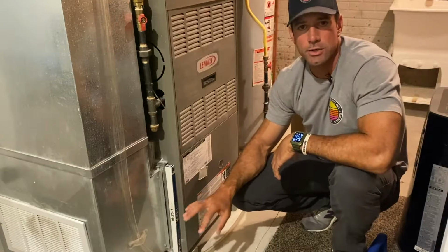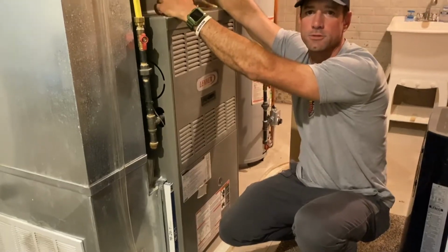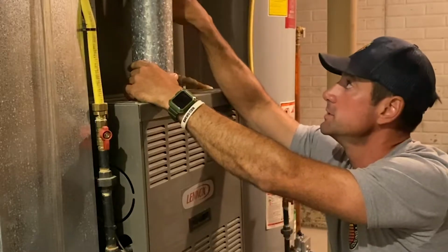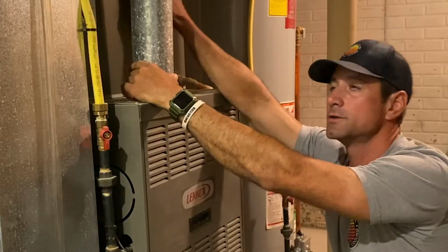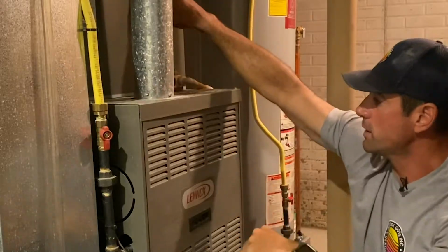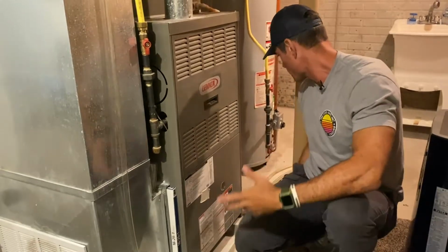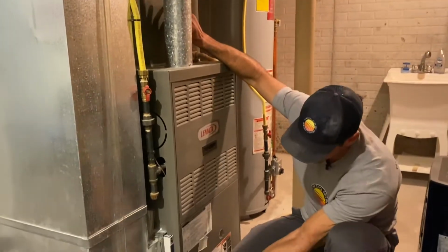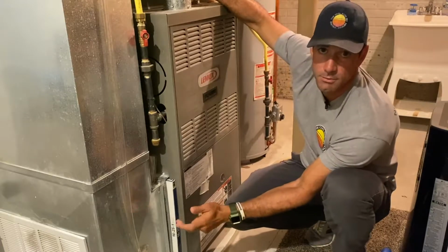If it gets too dirty, then your coil will get too cold. So your coil up here won't have the warm air from the house blowing over it. Basically, it just doesn't have that warm air, so it just gets colder and colder. Once it gets to freezing temperatures, all the condensation from your house freezes onto the coil, turns it into a block of ice. At that point in time, you'll notice water on the floor around your furnace. You'll be like, where's this water coming from? A lot of times it's from a frozen coil, and it's caused a lot of times from a dirty filter. There can be other causes, but those are going to be too technical.